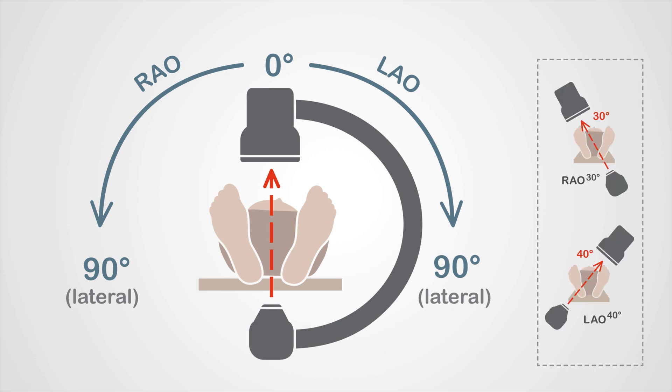Here are two example views. Using our key, you can see that in this picture the image intensifier has rotated 30 degrees to the right, and so we name this RAO 30 degrees, or RAO 30 for short. In the bottom image, the image intensifier has rotated 40 degrees to the left of the patient. We note that as LAO 40 degrees, or LAO 40 for short.